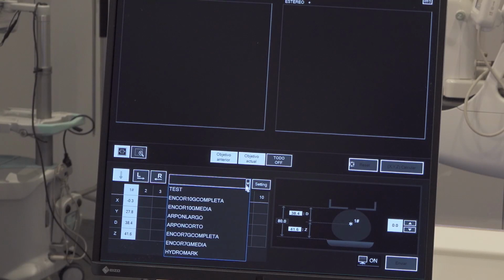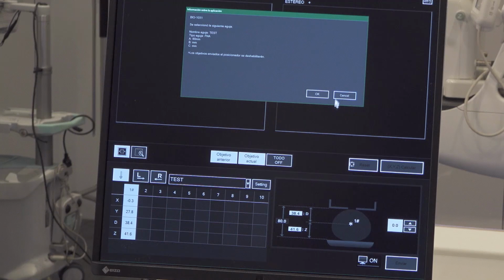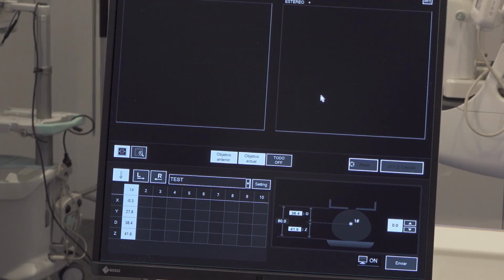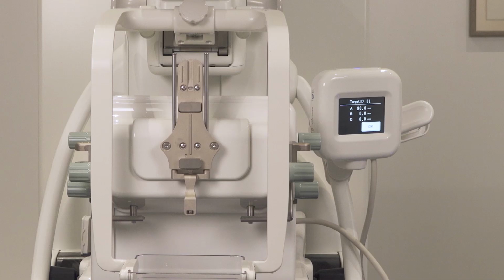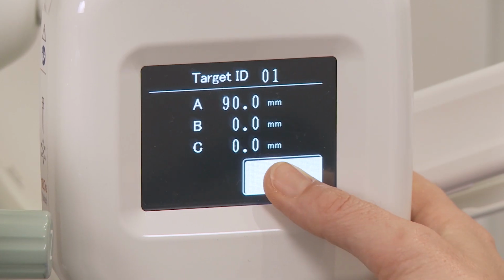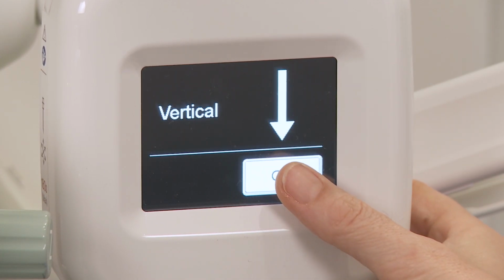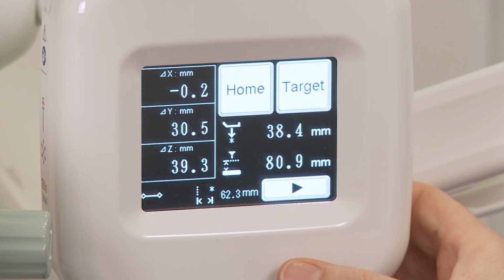Open the needle drop-down menu and select the test calibration needle. Confirm selected needle values. Click the Send button to send coordinates and needle characteristics to the biopsy positioner. The operation panel shows the target ID and calibration needle length. Press OK to confirm. Press OK to confirm vertical approach. The target information is displayed.